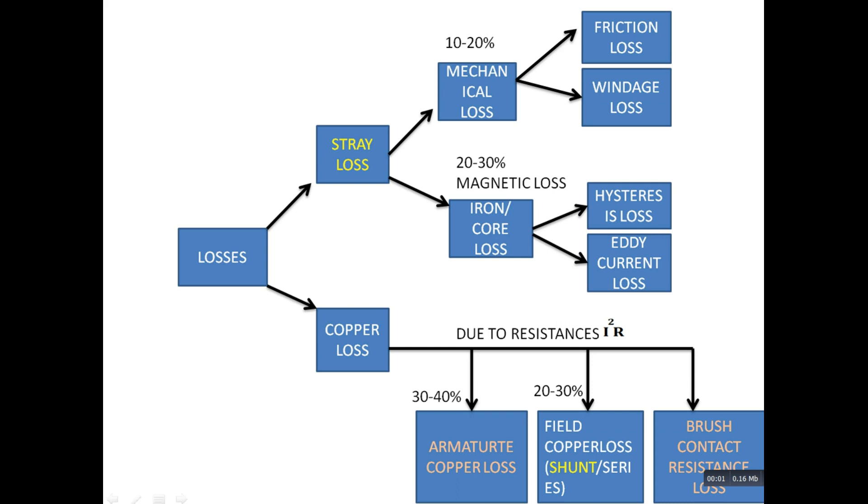Mechanical losses are 10 to 20 percent of full load losses. Iron loss is 20 to 30 percent, called core loss, and it is a magnetic loss. It can be further divided into hysteresis loss and eddy current loss.